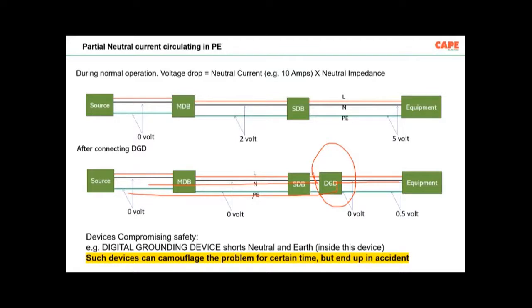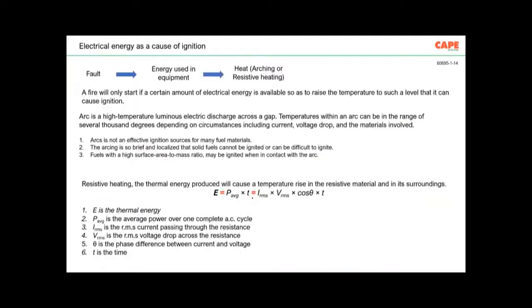As a result, you will have fire, you will have electromagnetic problems, you will have short circuit, and basically you will end up with an accident. So this is one of the issues. If you go to your industry, or if you check an industry, since I have conducted a lot of safety surveys, I know that for electrical engineers, shorting neutral and earth is sometimes a big solution, but that is actually a big mistake.